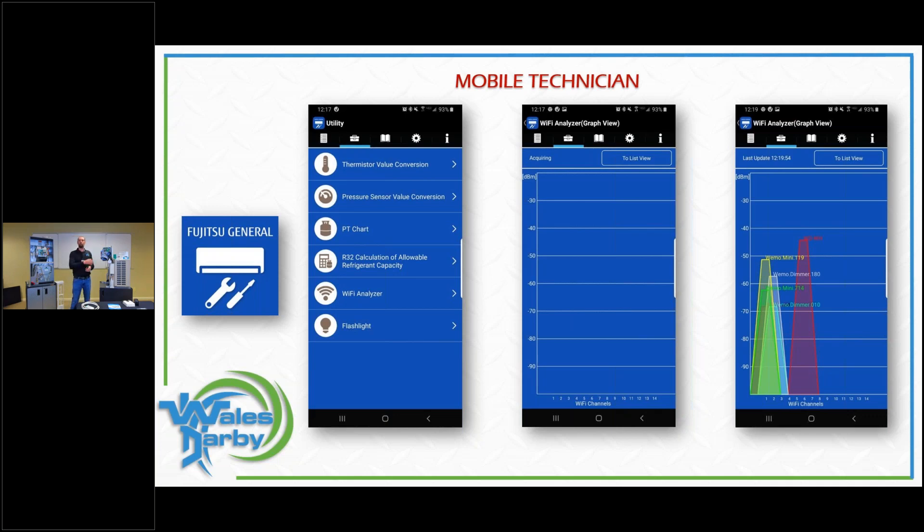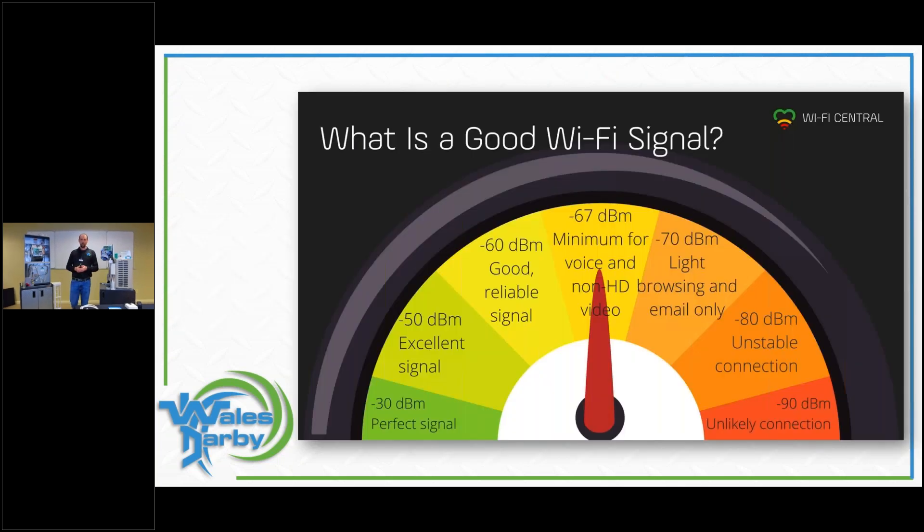Go next to each indoor unit you're going to hook Wi-Fi up to and make sure you have a strong, clear signal. For reference, from wificentral.com: minus 67 dBm is a good signal. The higher the number, the stronger the signal — so you want to be around minus 60 to minus 67 to have good confidence that the signal will work right at the indoor unit.